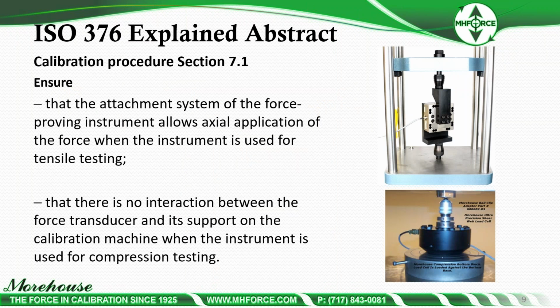Section 7.1 starts the calibration procedure and says, ensure that the attachment system of the force proving instrument allows axial application of force when the instrument is used for tensile testing, and that there is no interaction between the force transducer and its support on the calibration machine when the instrument is used for compression testing. In the picture above, this is a multi-axis load cell in our calibrating machine. When we discuss these adapters, we have sphericals, two sets of sphericals, where I'm highlighting in line with this to help ensure that the force is applied in the axial orientation. And then in compression here, we use a hardened ball adapter, and this is in our dead weight frame. It's a ball clip and a Morehouse ultra precision cell flat on a block for compression.